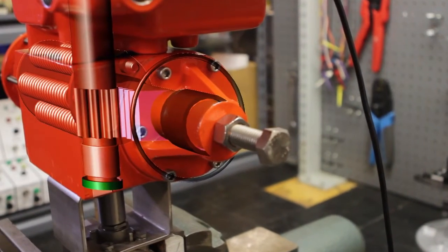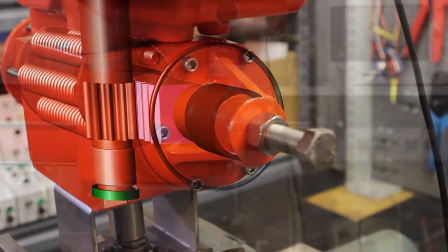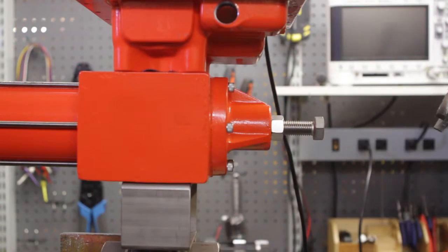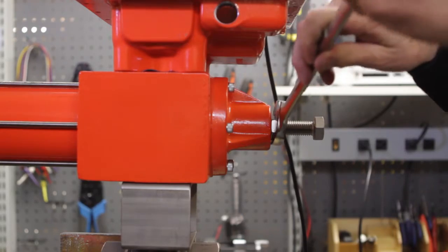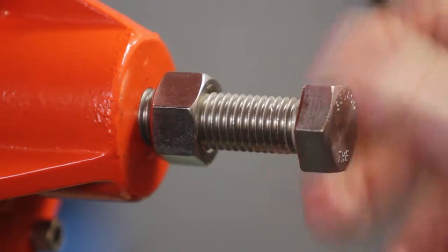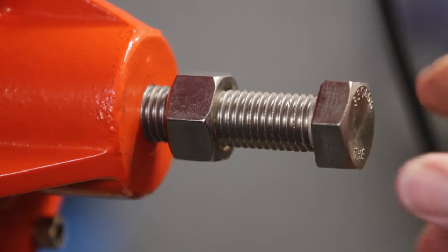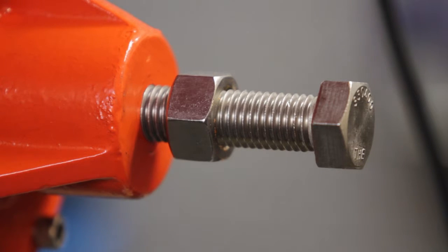This is done to assure that during normal operation, the actuator is not driven into the mechanical stop. Using the 1-1/8 inch open end wrench, loosen the jam nut on the mechanical stop and back the screw out several turns. This is done so that while setting the closed position, you do not inadvertently run the actuator into the mechanical stop.